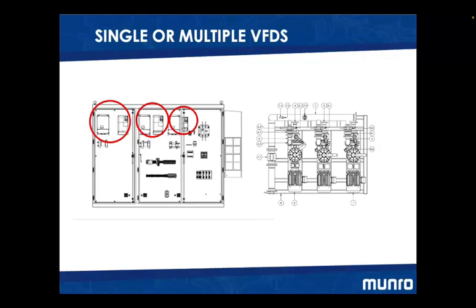We could start to see some overpressuring in the system. We may have to add valves to the irrigation system so that we can throttle the pumps to keep them from either overloading or overpressuring the system because of the loss of the variable frequency drive.